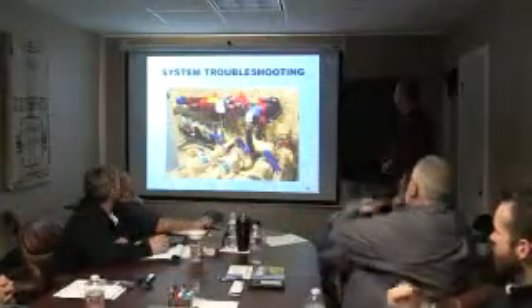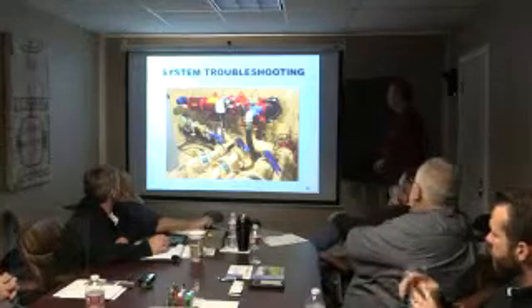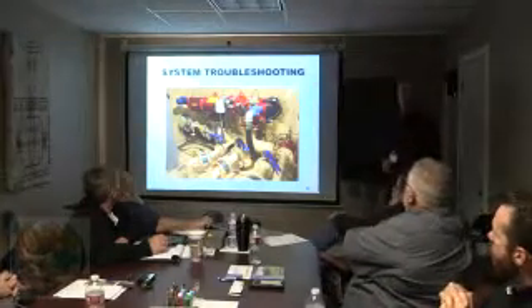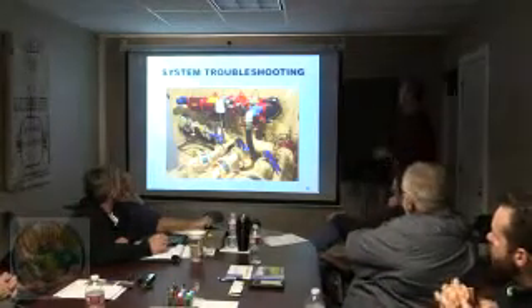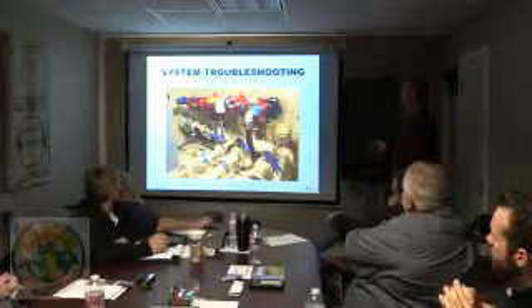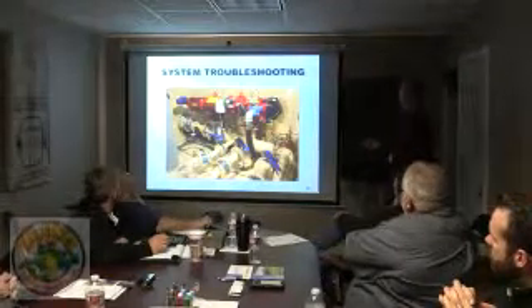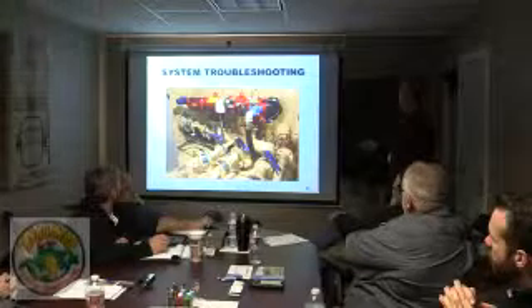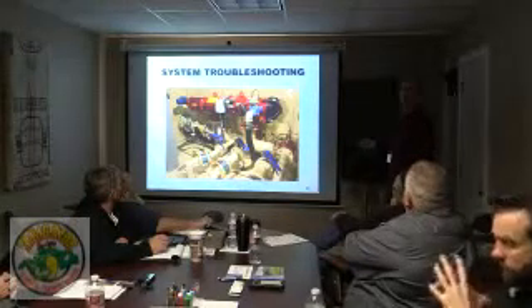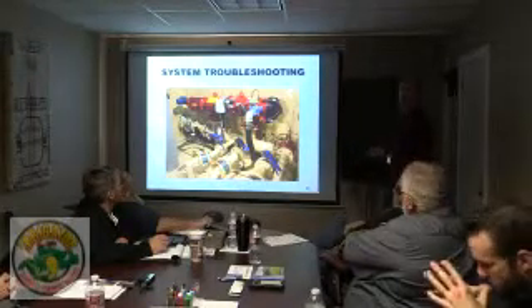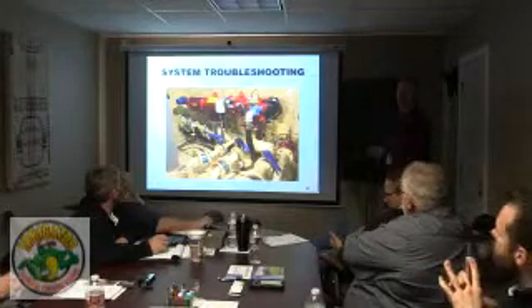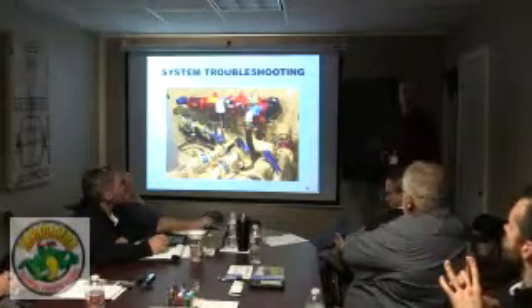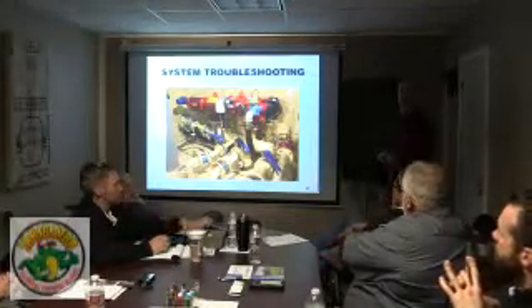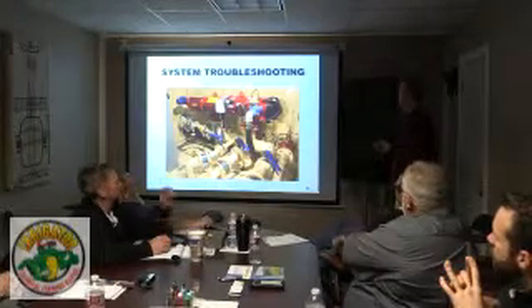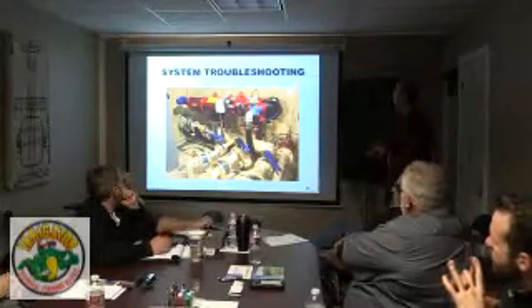Troubleshooting. We'll take a look at an actual pump station now and just kind of a little bit of troubleshooting some of the components on that. On this one, we've got an amiad filter. We'll look at the scanner motor. That's what I was talking about. It makes the suction scanners in that filter go back and forth. We'll show the inside of one of these so you'll see what I'm talking about if you've never seen an amiad before or had one opened up apart.